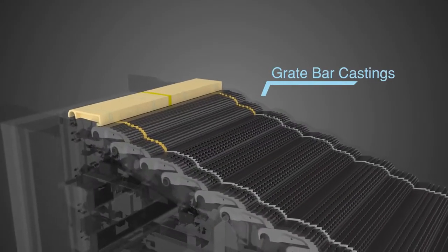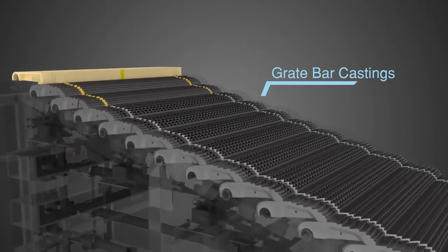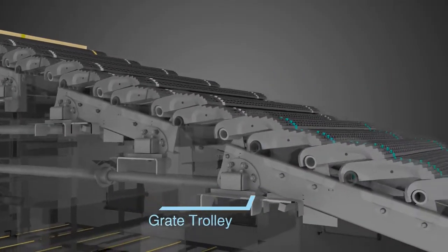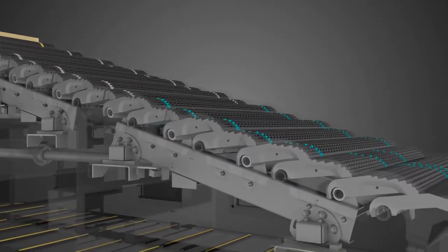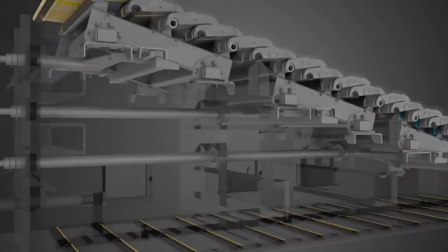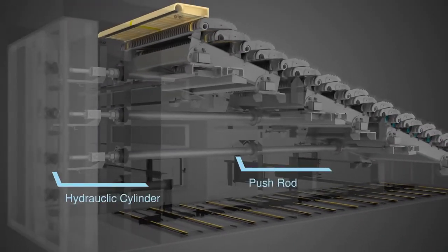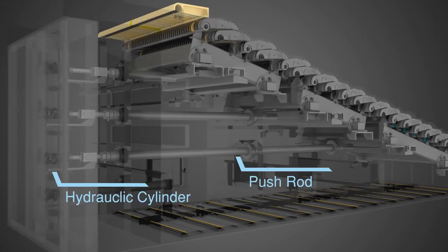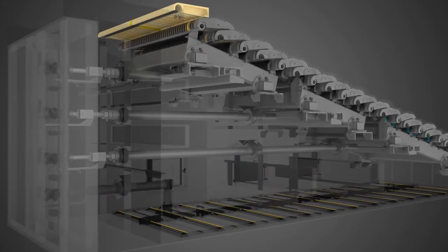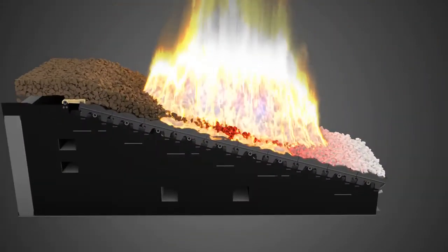Reciprocating grate utilizes successive oscillation of grate castings mounted on different trolleys for the continuous movement of fuel. These trolleys are driven by independent hydraulic cylinders. Alternate movement of grate blocks pushes the fuel in the distinct combustion zones of the grate.